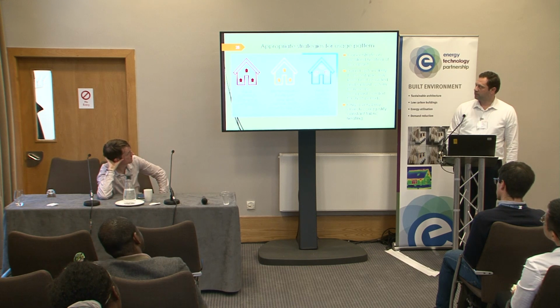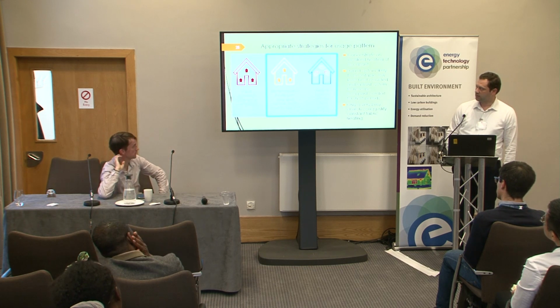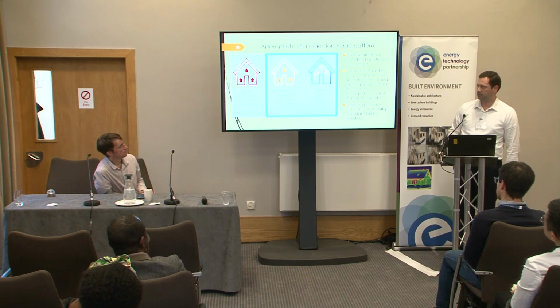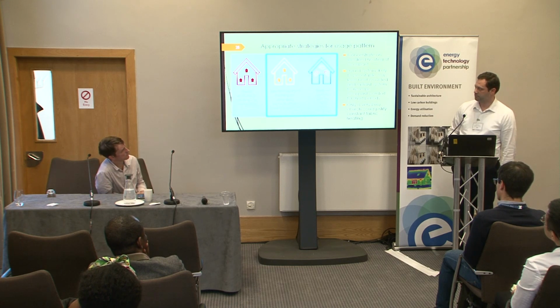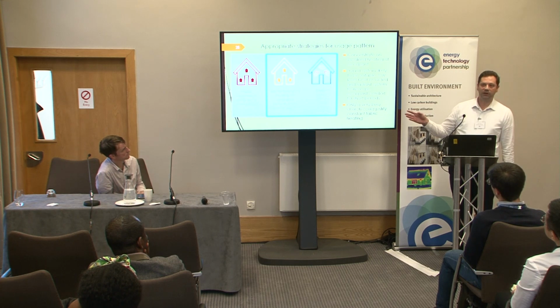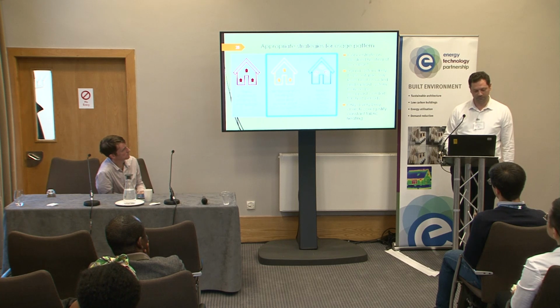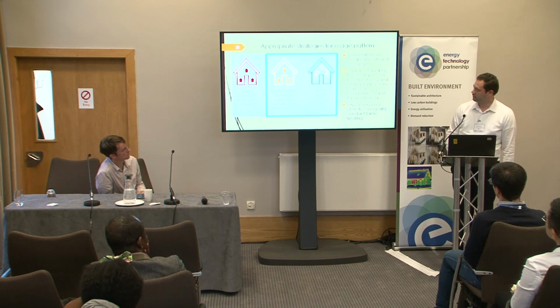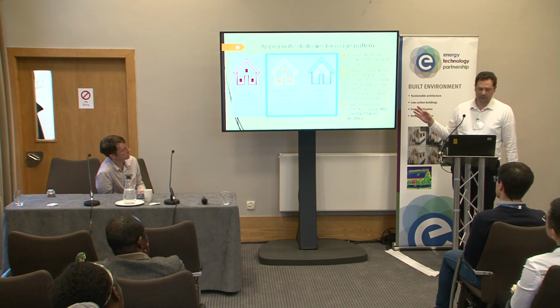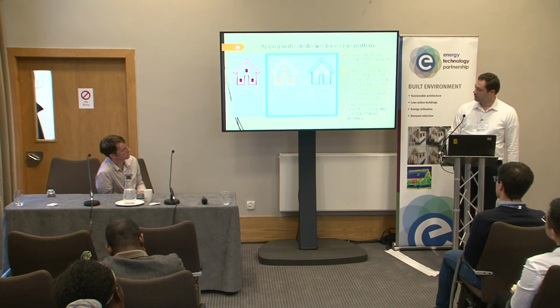We're really looking for these two strategies together: low temperature heating for extended periods of time and a radiant system. Rapid increases in air temperature for short periods is what we've been trying to do for years, mainly without much success, because churches are generally cold despite all the energy we fling into them in the heating. So it's looking at heating the people, and the national churches have said that. Don't heat your building fabric, heat the people.